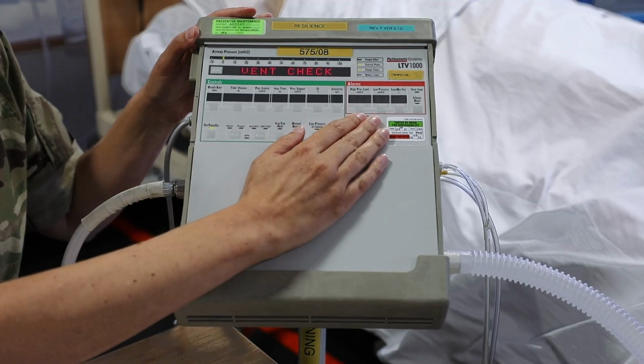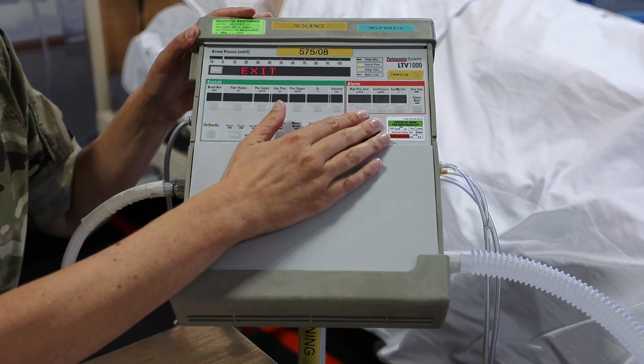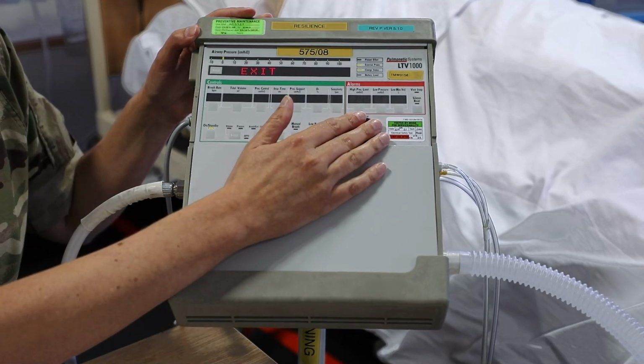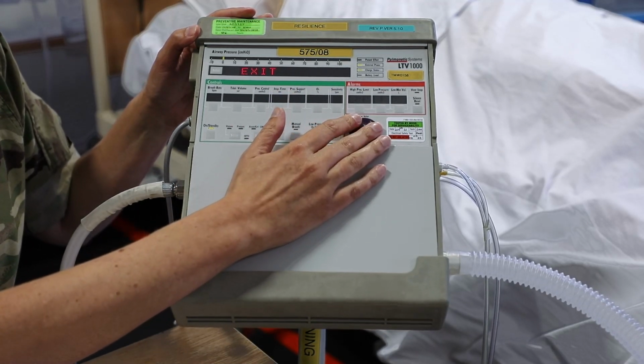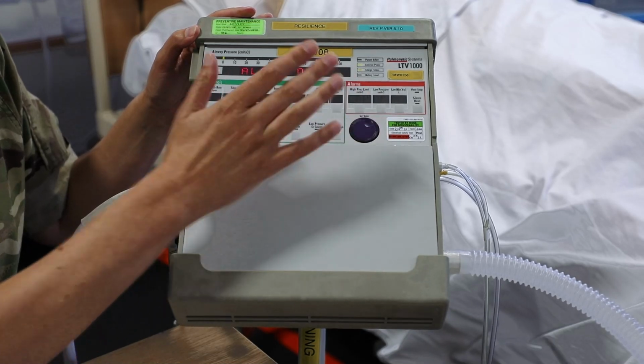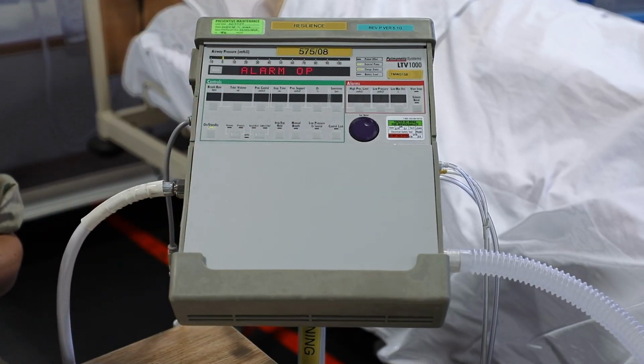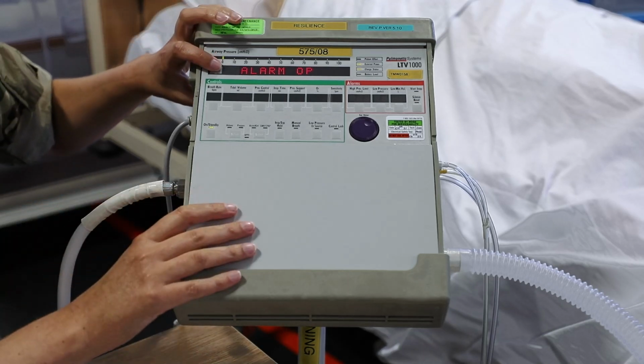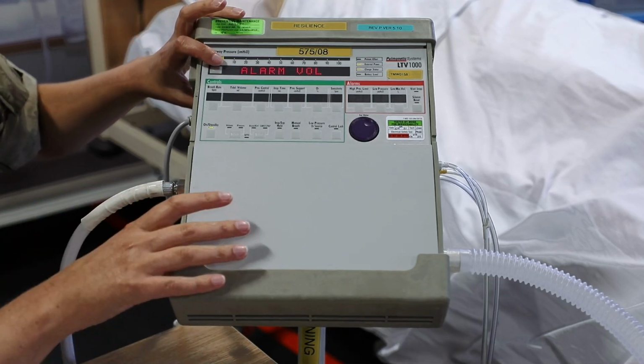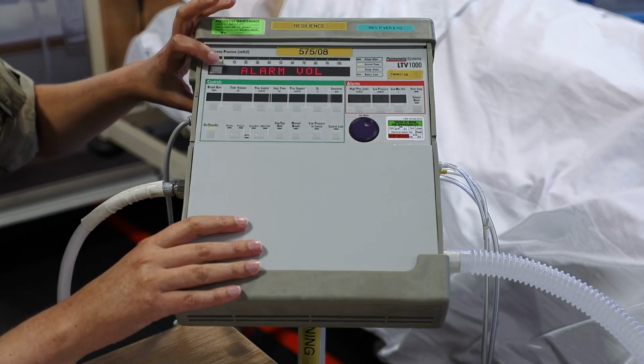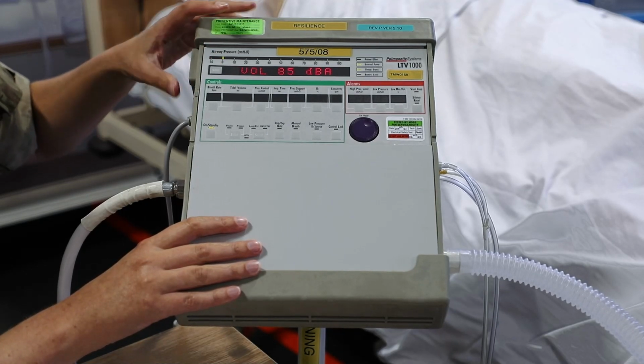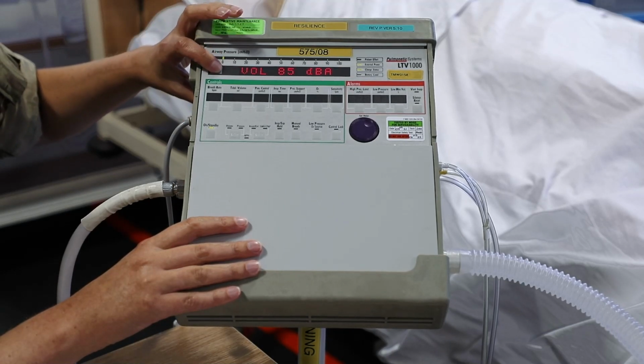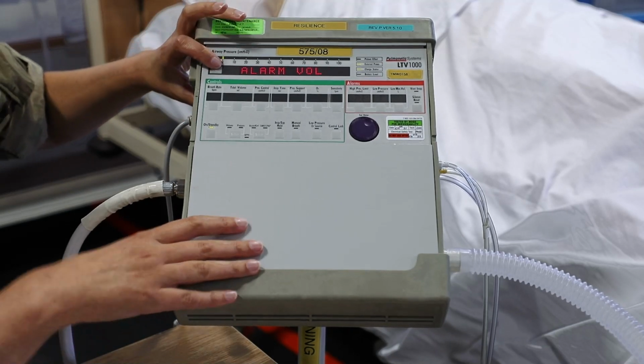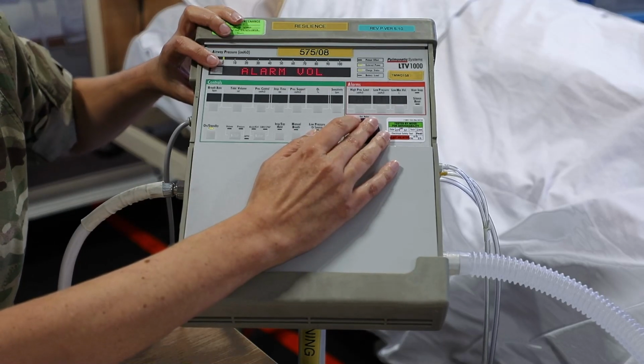And next we're going to move on to our alarm operation. So if we turn the dial clockwise, it does take us to an exit menu. Don't worry, just turn it clockwise once more and you get through to the alarm operations. In here, if we press select, the first option is to confirm what the alarm volume is. If you press select, it should be 85 decibels, which it is, so that's correctly set. Press select again to go back up to the previous menu.